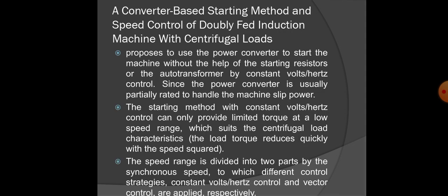The purpose is to use the power converter to start the machine, instead of using a starting resistor and auto transformer, by constant voltage and frequency control. Since the power converter is usually partially rated to handle the machine slip power, the starting method with constant voltage and frequency control can provide limited torque at the low speed range, which suits the centrifugal load characteristics, as the load torque reduces quickly with speed squared.